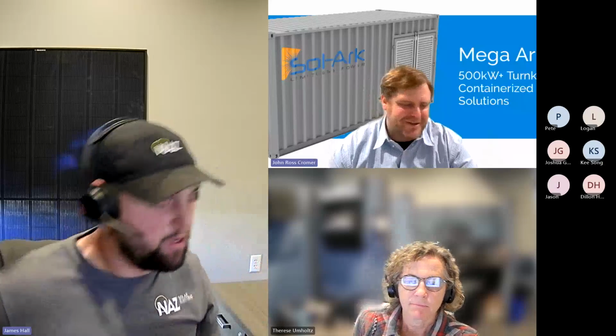There's pros and cons to having a shared DC bus amongst all the batteries in the system, but at the end of the day, it does create a bit of a safety hazard to just put in as many lithium batteries as you can onto a DC bus and energize it. This breaks up that safety hazard. From the scale of these projects, it definitely makes more sense to do it this way.